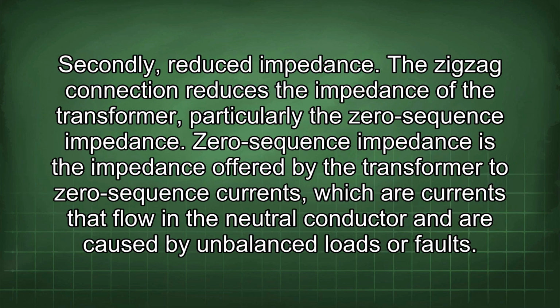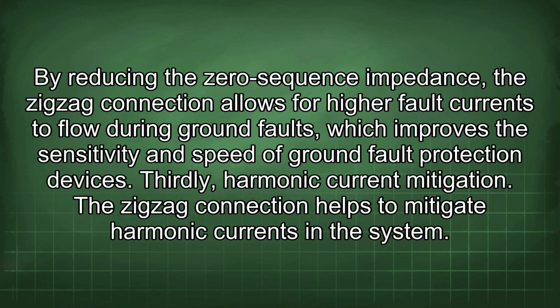Secondly, reduced impedance. The zigzag connection reduces the impedance of the transformer, particularly the zero-sequence impedance. Zero-sequence impedance is the impedance offered by the transformer to zero-sequence currents, which are currents that flow in the neutral conductor and are caused by unbalanced loads or faults. By reducing the zero-sequence impedance, the zigzag connection allows for high fault currents to flow during ground faults, which improves the sensitivity and speed of ground fault protection devices.